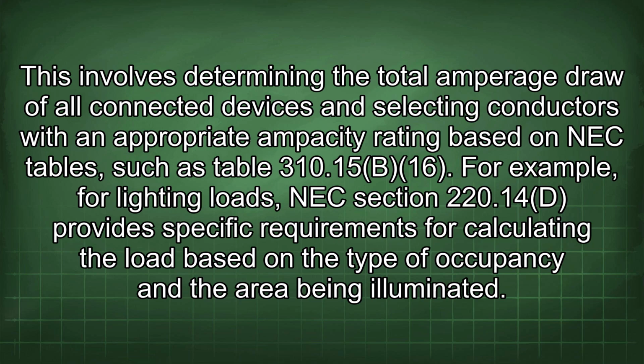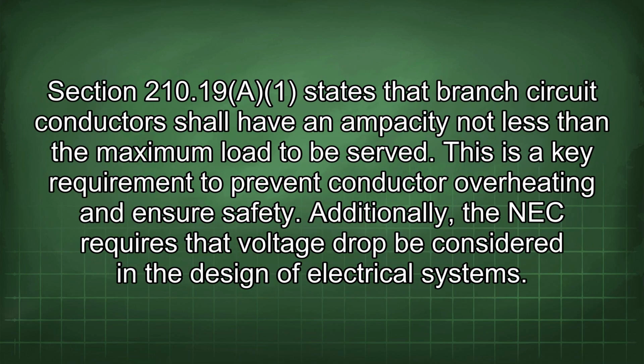For example, for lighting loads, NEC Section 220.14(D) provides specific requirements for calculating the load based on the type of occupancy and the area being illuminated. Section 210.19(A) states that branch circuit conductors shall have an ampacity not less than the maximum load to be served. This is a key requirement to prevent conductor overheating and ensure safety.